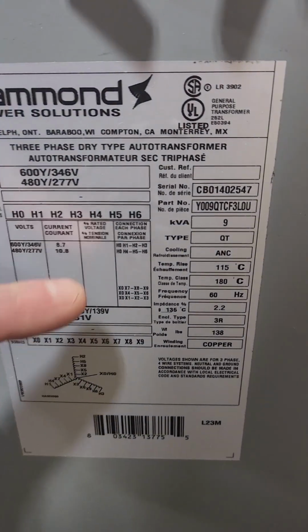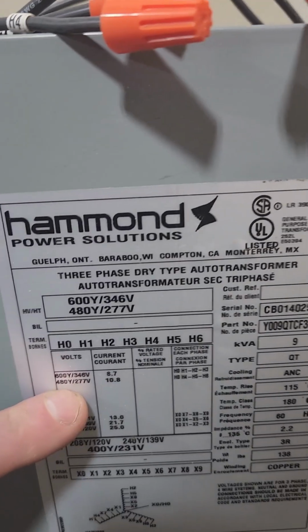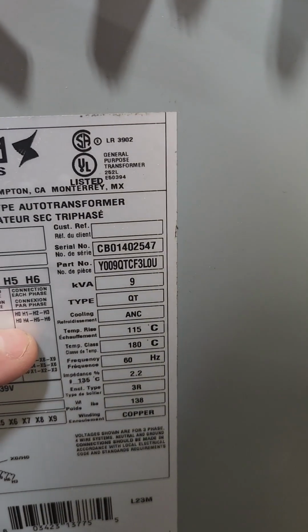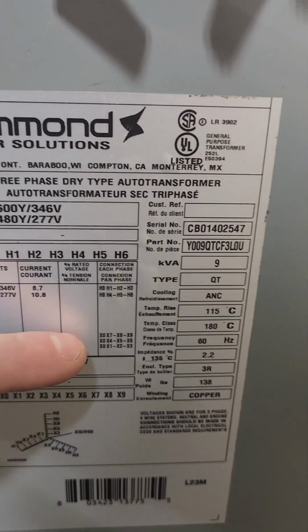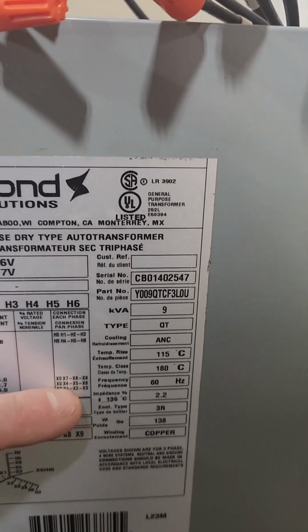So the nameplate on this transformer is going to tell us which of these wires we need to wire. For the input side on the 480, we need H0, H4, H5, H6. And to get our 240 out, we're going to wire X0, X4, X5, X6.